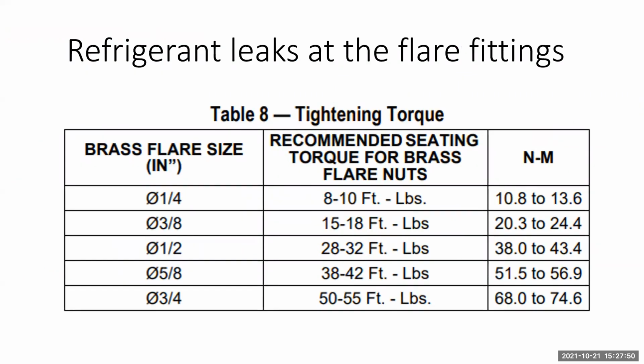So if you have a leak, you're low on refrigerant and you can't find the leak, it's a good bet that more than likely it's your flare nuts. That's why it's always a good idea to torque them to the correct settings, with a torque wrench and a backup wrench. You can put some oil on there and make sure you're not spinning the pipes. What it does is it expands and contracts just enough for you to lose a little bit of refrigerant. So that's always something to look for. You can look around there, obviously, for oil and stuff like that. But if you find that you're low on refrigerant and you can't find the leak, go get yourself your torque wrench and reset those flares.